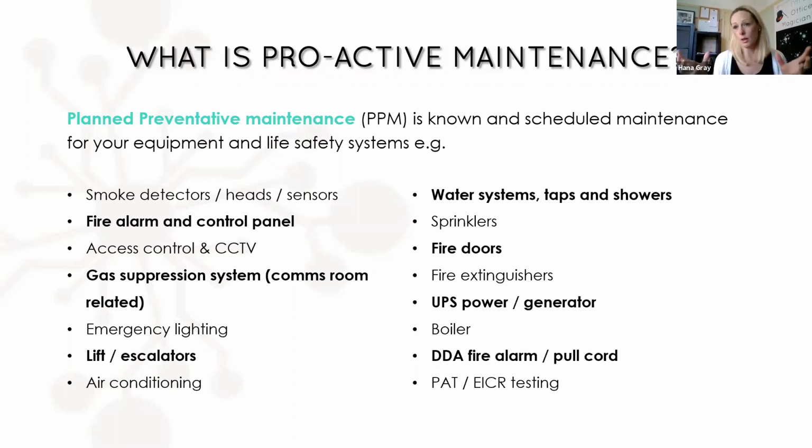It's looking at things like the seals and making sure that they're still compliant and they're still in working order, because they are a fire safety measure. They will have been put in your building or in your demise for a reason, to hold back a fire, to contain a fire, and stop it spreading as quickly, and give you 30 minutes or 60 minutes, whatever rating that door might have. So it's important, just much like you would a fire extinguisher, to maintain those doors and check for any issues, closing times, as well as the seals and things.